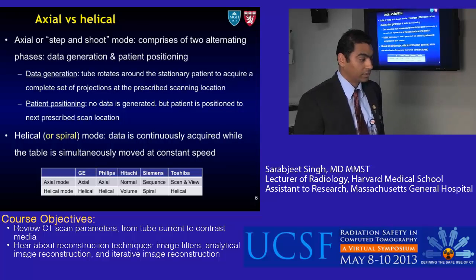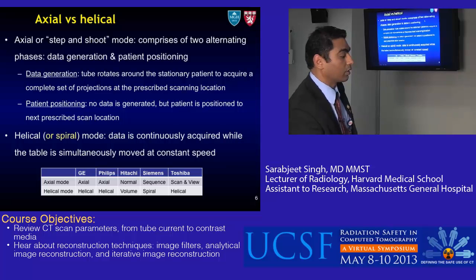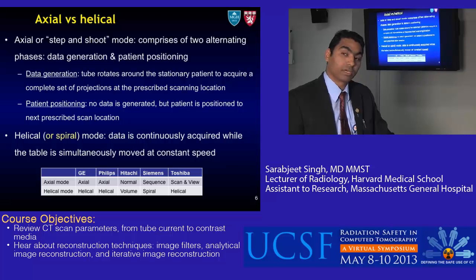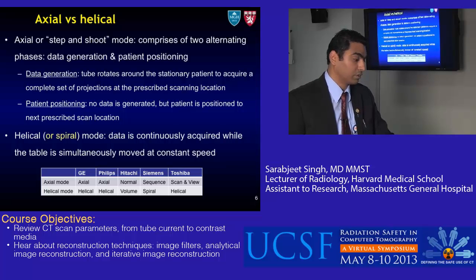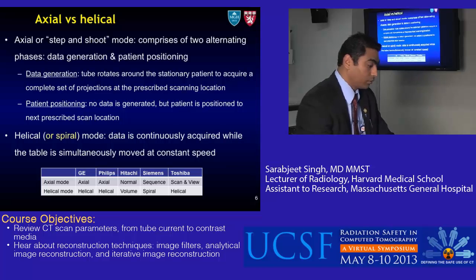Next we move to axial versus helical mode. Axial, or step-and-shoot mode, comprises two alternating phases: data generation and patient positioning. In the data generation phase, the tube rotates around the stationary patient to acquire a complete set of projections at the prescribed scanning location. In patient positioning, no data is generated — the patient is moved to the next prescribed scan location. In helical mode, data is continuously acquired while the table simultaneously moves at a constant speed. Almost all vendors call it helical, except Hitachi which calls it volume mode.